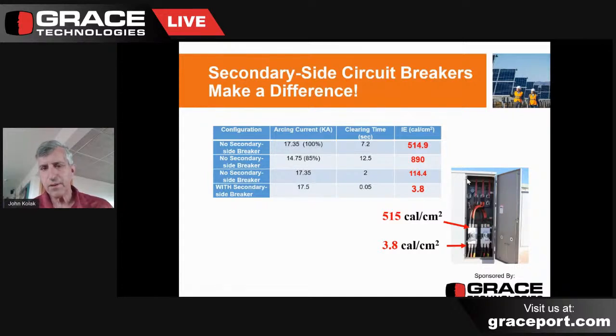So here we see a few different scenarios. If we're on the side of that circuit breaker that's connected directly to the low voltage winding in the transformer, the overcurrent protection is only seeing a fraction of the fault current that you're seeing on the low voltage side, and we'll show you that in just a minute. If we calculated that out at 100% of the arcing current, it would calculate to 515 calories of incident energy on the secondary side or the low voltage side of that transformer. If we calculated that at the 85% level, it would increase up to 890 calories.